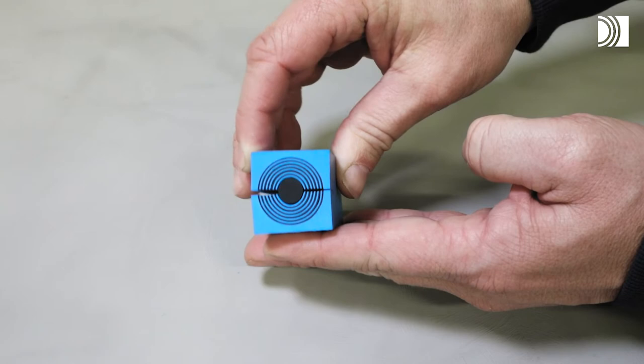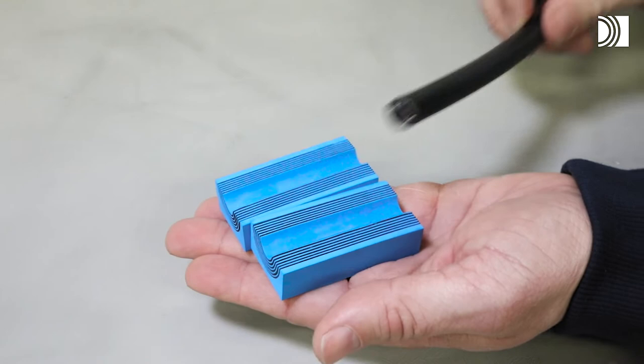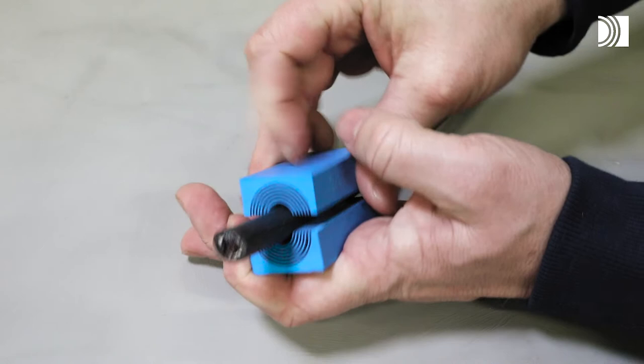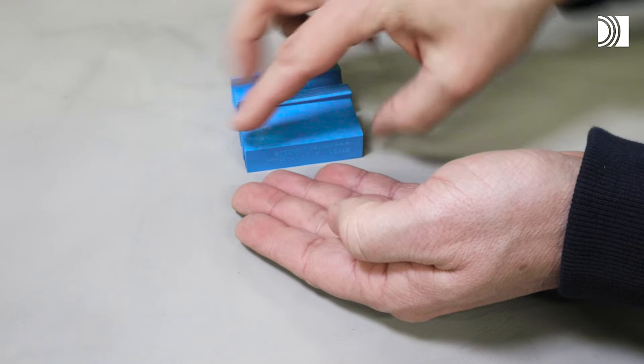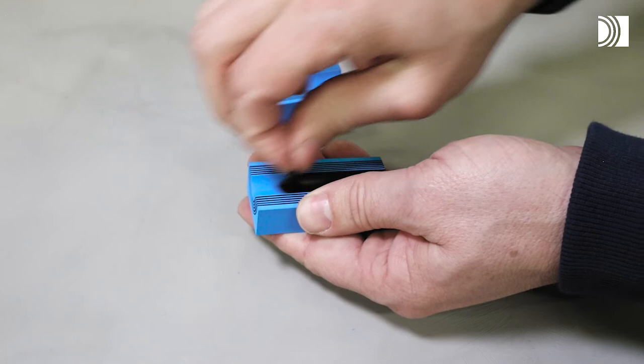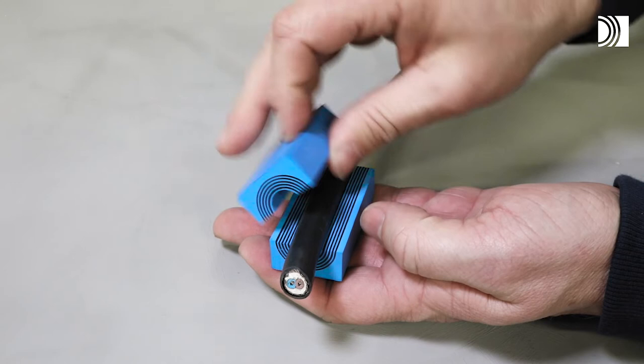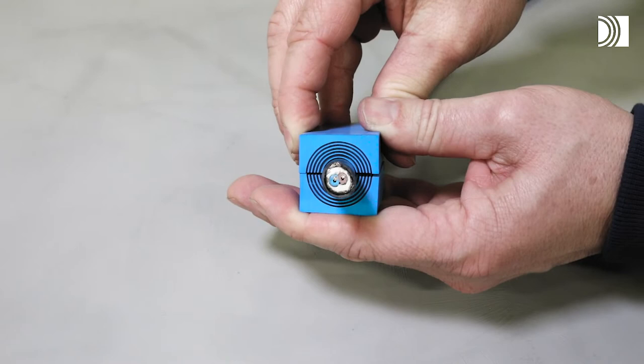Adapt the modules. Peeling off the layers. Adapt the modules by peeling off layers. Achieve a 0.1 to 1 mm gap between the two halves when held against the cable or pipe. The number of layers may not differ by more than one between the corresponding module halves.